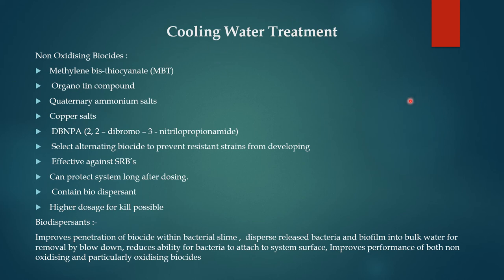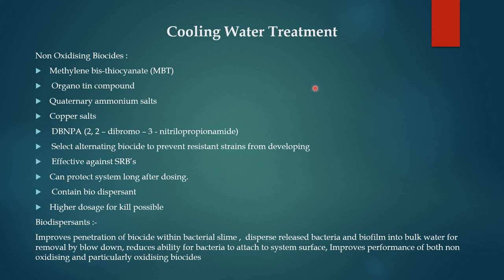When non-oxidizing biocides are used in open-type cooling towers: stop chlorine dosage for 24 hours, reduce or close makeup water and stop blowdown, dose non-oxidizing biocides and circulate for 24 hours. The next day, increase blowdown to reduce TDS to the required level, then resume routine makeup water and chemical dosing. Non-oxidizing biocides are used once every 15 days or once a month.